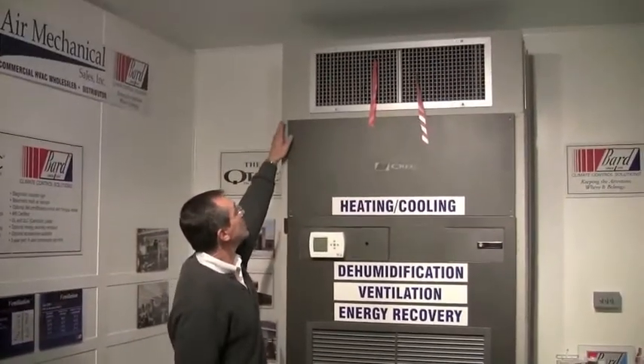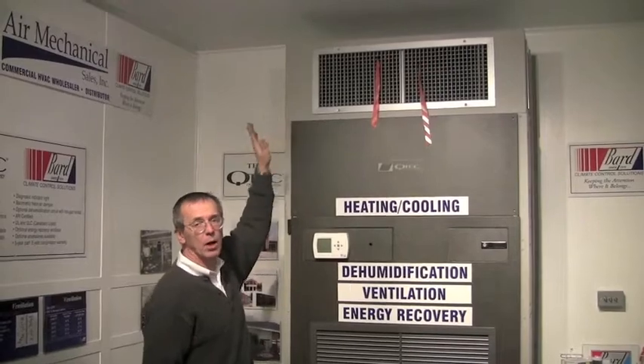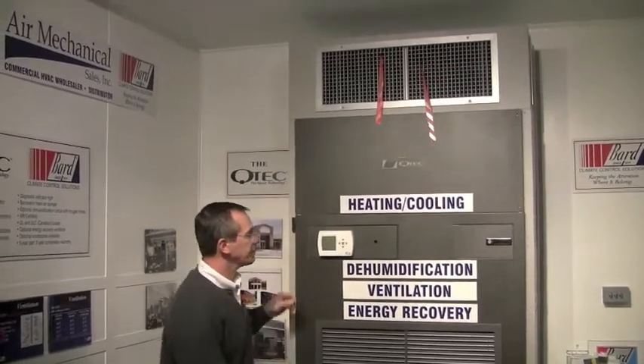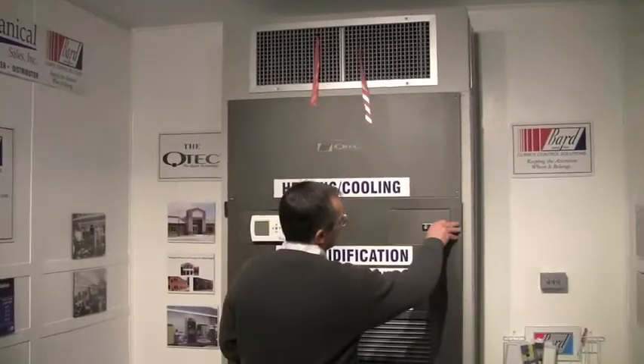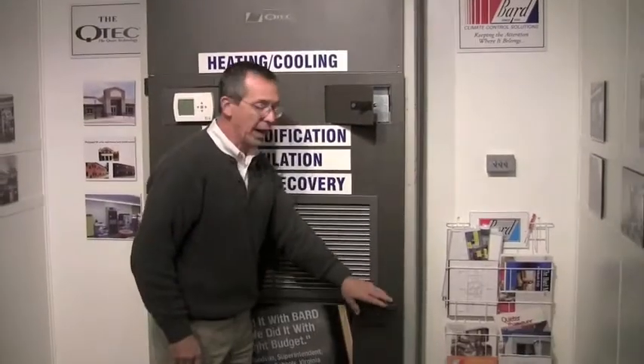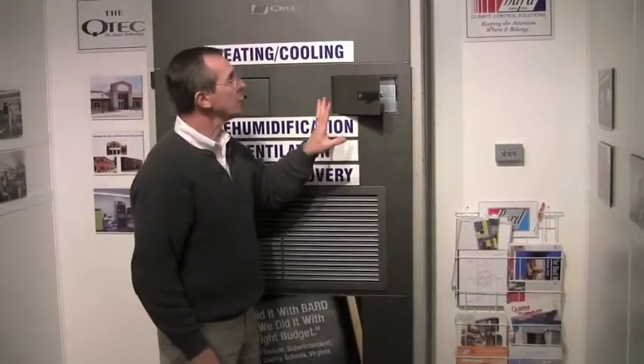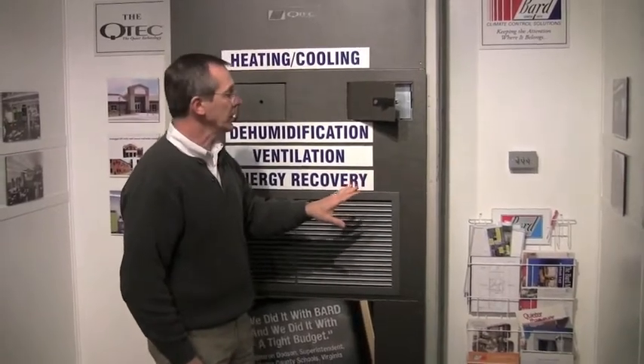It's also available as a duct application. Now you hook ductwork to the top of the unit. In that case, we have a duct package that covers from the top of the unit all the way to the ceiling. The unit has a screw in here, and I've already taken the screws out of most of the front of the unit just for ease of getting into it and quickness.